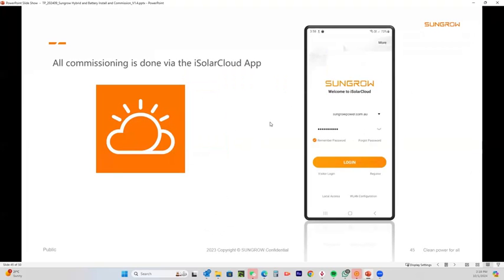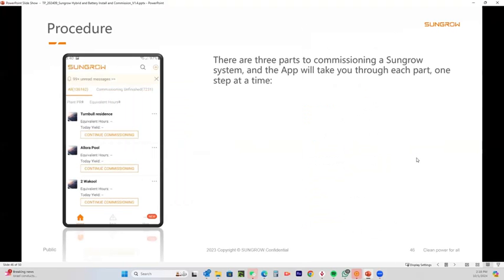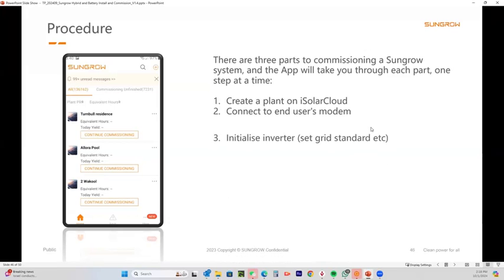All commissioning is done via the iSolar Cloud app, so if you don't have an iSolar Cloud account, you need to register as an installer to get your account. There are 3 parts to commissioning, it's dead easy. The first thing you're going to do is create a plant on iSolar Cloud. You're going to connect to the end user's modem and through to the internet, and then you're going to initialize the inverter, i.e. set the grid standard, okay?